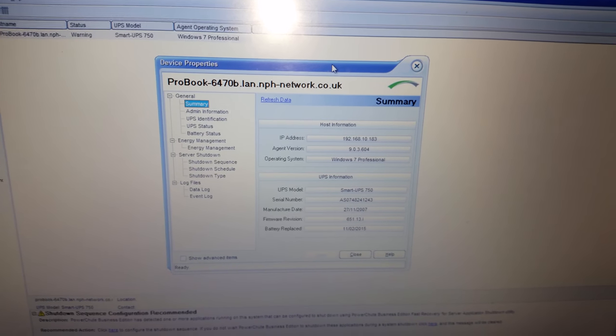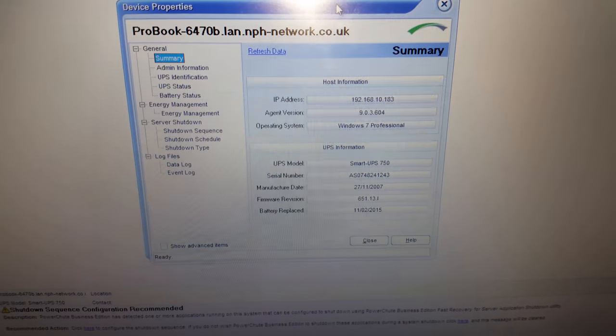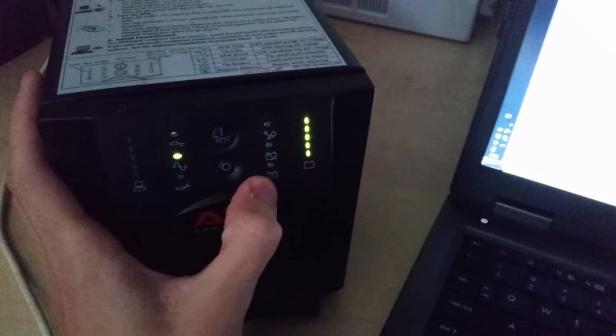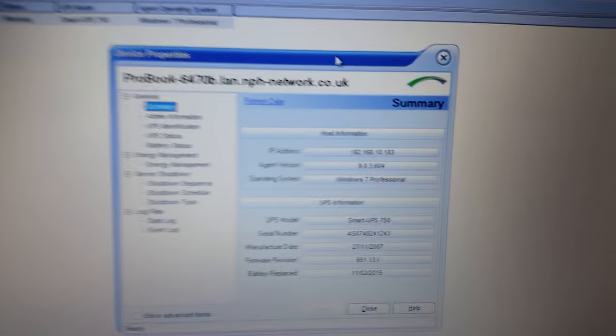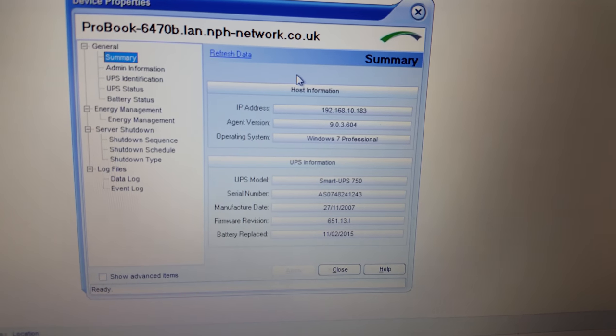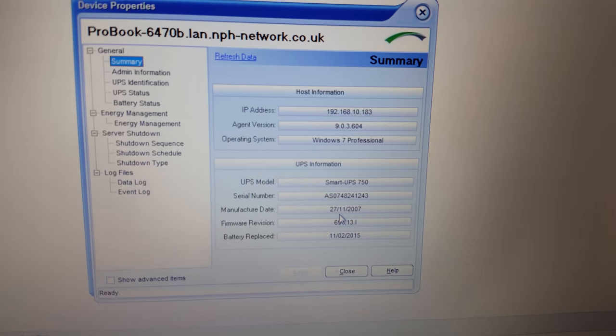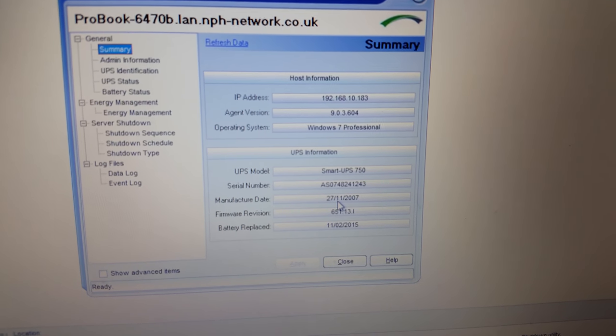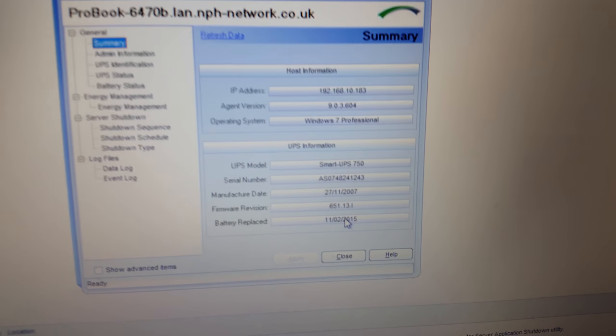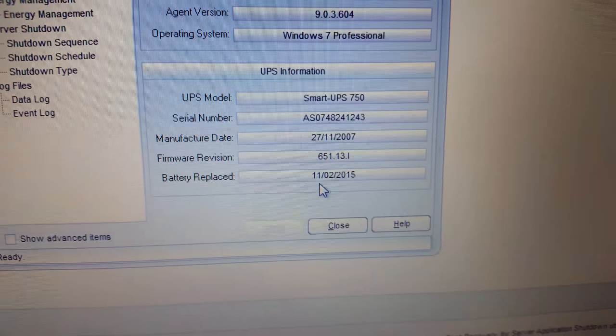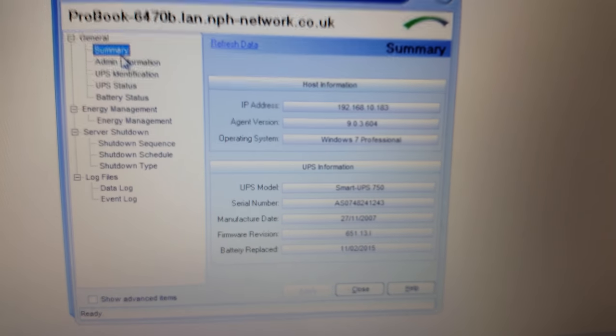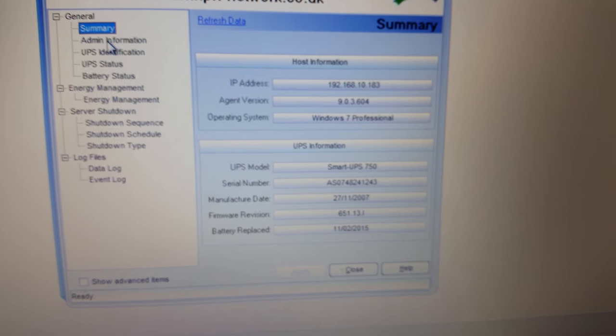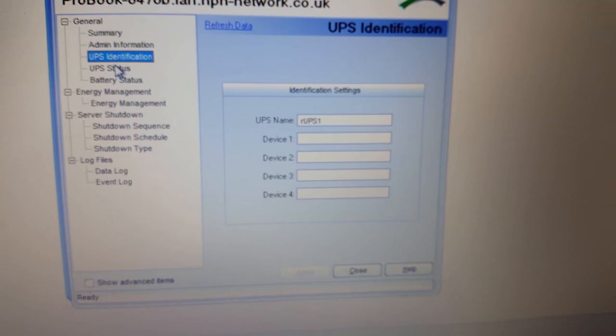This software is used to manage these UPS units. Something that's quite interesting is that it's not showing the battery error anymore. I thought the batteries in this unit were about a year old, but it seems they're actually older than that. You can see the UPS itself was made 27th of November 2007, so it's quite an old unit. But the battery replaced date is set to the 11th of February 2015, so I've actually had these for two years now, two and a bit, almost two and a half years.